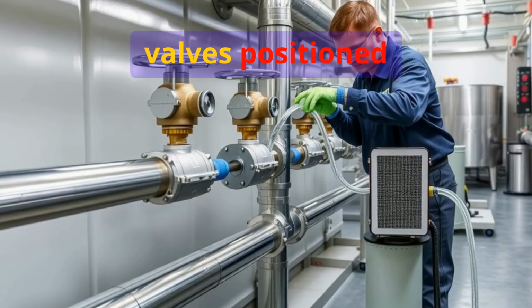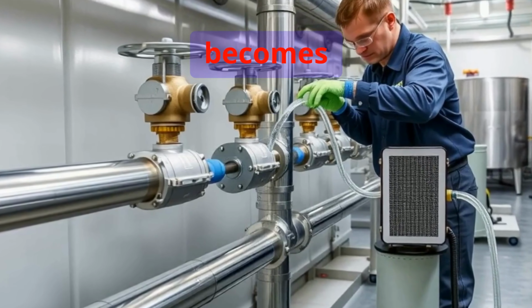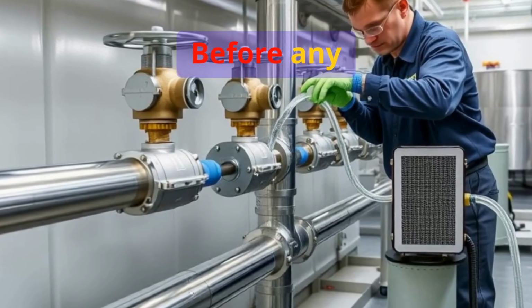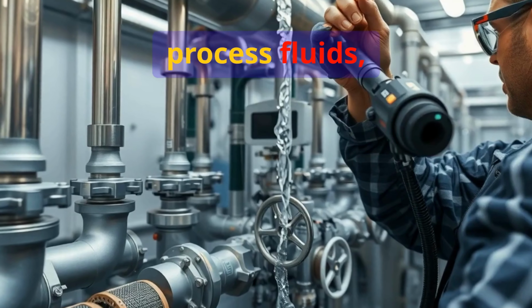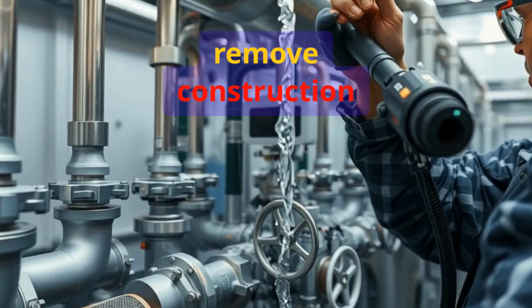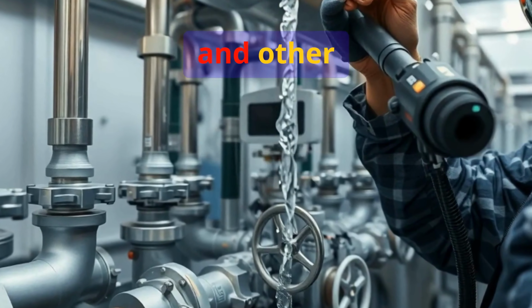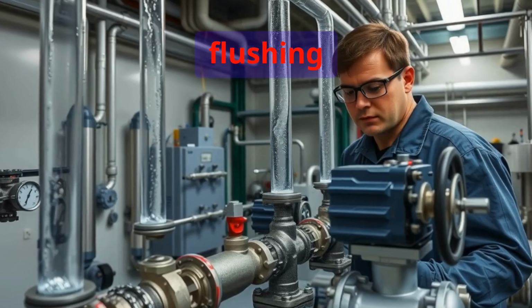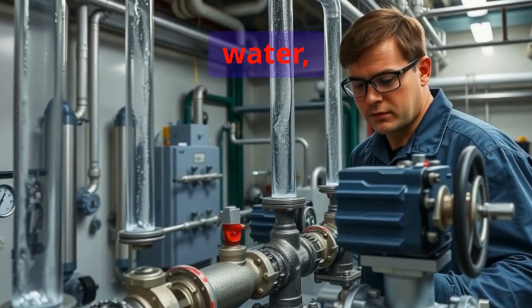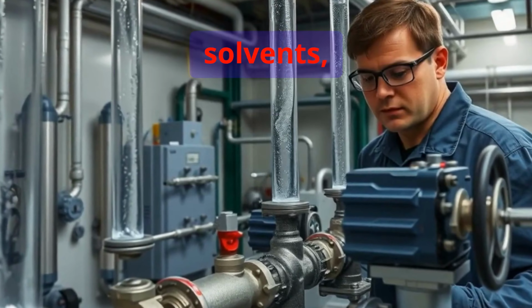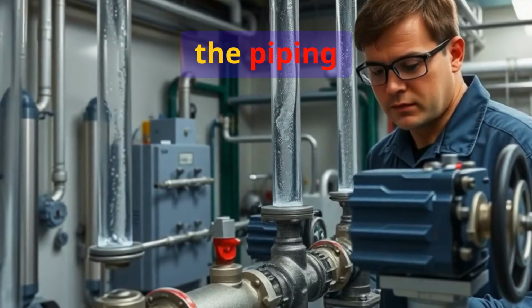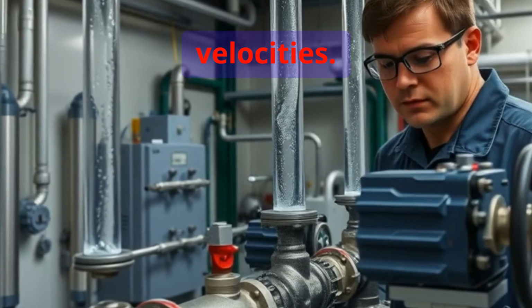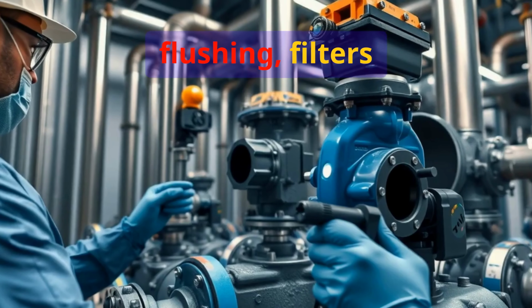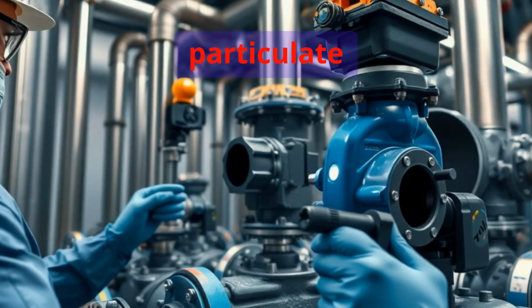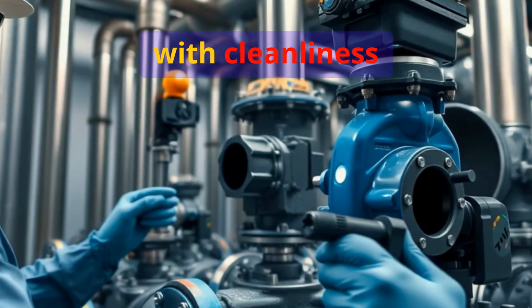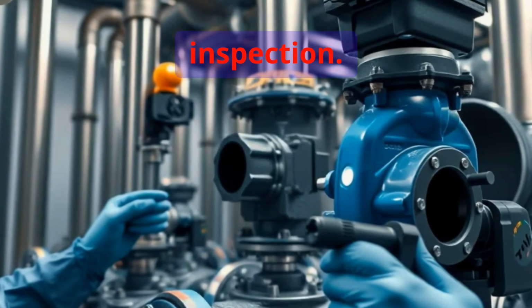With the valves positioned and secured, cleanliness becomes the next priority. Before any system is introduced to process fluids, it is essential to remove construction debris, dust, scale, and other contaminants. Specialized flushing procedures utilize either water, air, or process-compatible solvents, circulated through the piping and valve internals at specified velocities. During flushing, filters or screens capture particulate matter, with cleanliness verified through sampling and visual inspection.